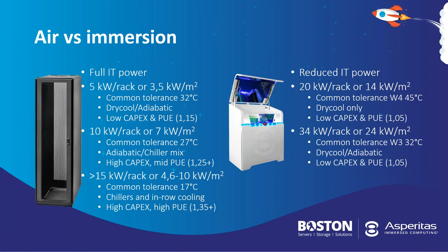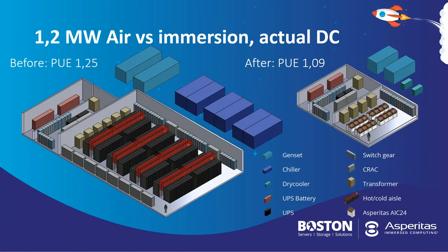If you raise that bar to 34 kilowatts with the upcoming CPUs, the next Intel generation coming up with chips going towards 400 watts, we can still facilitate that with at least 32 degrees Celsius water, potentially higher. Which is still feasible to run with dry coolers and adiabatics, at least in northern Europe. But it still allows the low capex and PUE effects. And these densities can only be achieved with immersion technology.